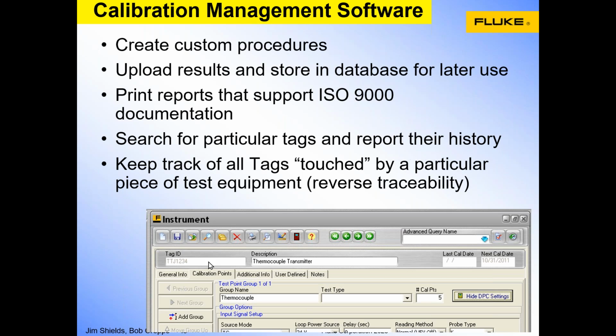In calibration management software, you can create custom procedures. For each tag number that you've identified that's critical in the plant, each tag can have its own procedure by tag number. With this software, you can upload results from a documenting process calibrator and store them in the database for later use or retrieval to show an auditor or quality inspector or some other entity or person in an organization that is looking for proof of a calibration on a particular instrument or tag. You can print reports to support ISO 9000 documentation.